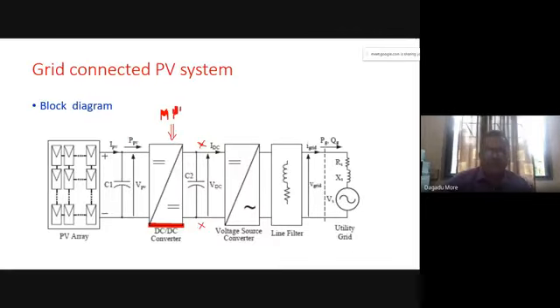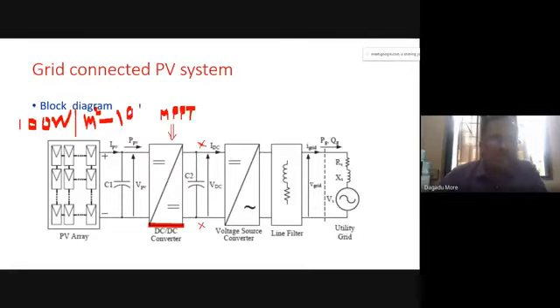There are various techniques to operate the panel at MPP. This is one of the requirements. Every solar system should always operate at the MPP, extracting the maximum available energy from the PV panel depending upon the solar radiation. Solar radiation may change, ranging from 100 watts per meter square to 1,000 watts per meter square, depending upon the radiation.